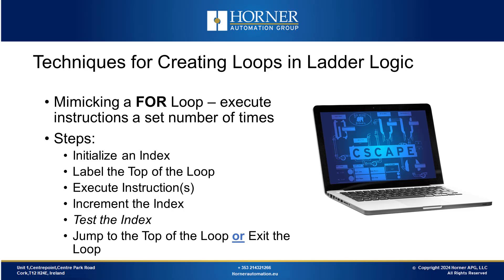Now let's look at some techniques for creating loops in ladder logic. Here we want to mimic for and while loops, as ladder logic does not have for or while instructions. Let's start with for loops, which execute instructions a fixed number of times. To mimic a for loop, we first need to initialize an index by creating a variable for it. We then identify where the top of the loop is, execute the instructions to be repeated, manually increment our index, test the index to see if we have reached the maximum number of iterations, jump back to the top if needed, or exit the loop if we have gone through the fixed number of times.